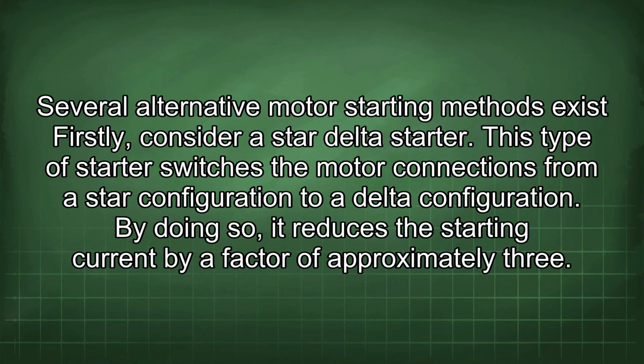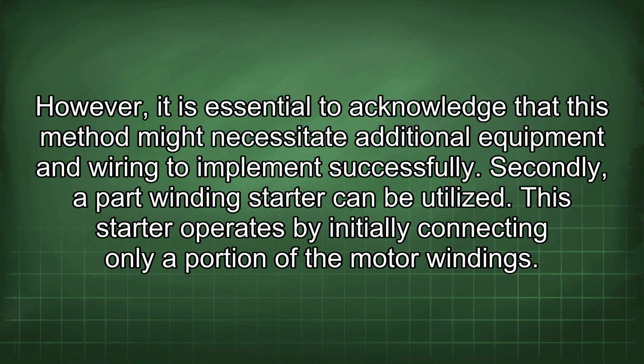Several alternative motor starting methods exist. Firstly, consider a star-delta starter. This type of starter switches the motor connections from a star configuration to a delta configuration. By doing so, it reduces the starting current by a factor of approximately 3. However, it is essential to acknowledge that this method might necessitate additional equipment and wiring to implement successfully.